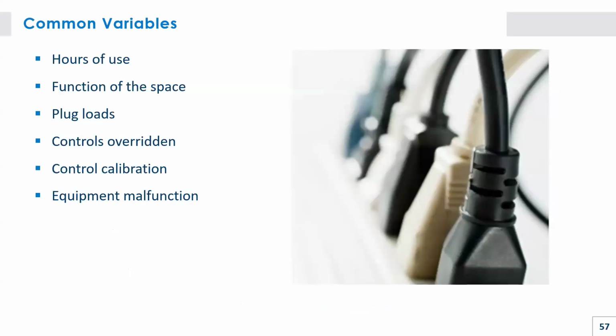So if you've learned that the energy use of your project has changed, there's no reason to panic. Some common reasons we found as to why the meter might differ from the model: hours of operation or use have changed, space is being used differently than expected, maybe higher plug loads weren't anticipated, controls have been overridden, calibration is off, or there's an equipment malfunction. This is rare, but it does sometimes happen.